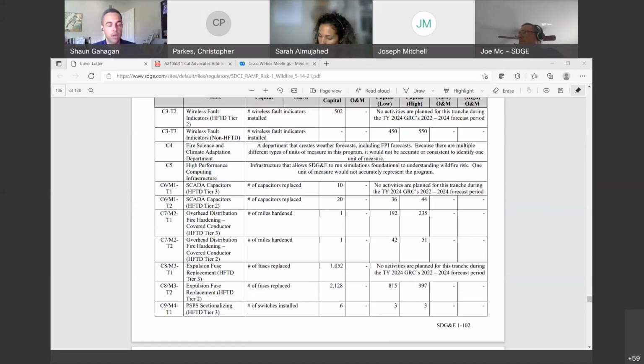We might have to do some more digging into the types of conductor we have and the faults we've seen. Based on what the firm team put together when they first started, they were looking at the wire down events and the types of failures on our system, and they identified the number 4 and number 6 copper as being the problematic conductors.